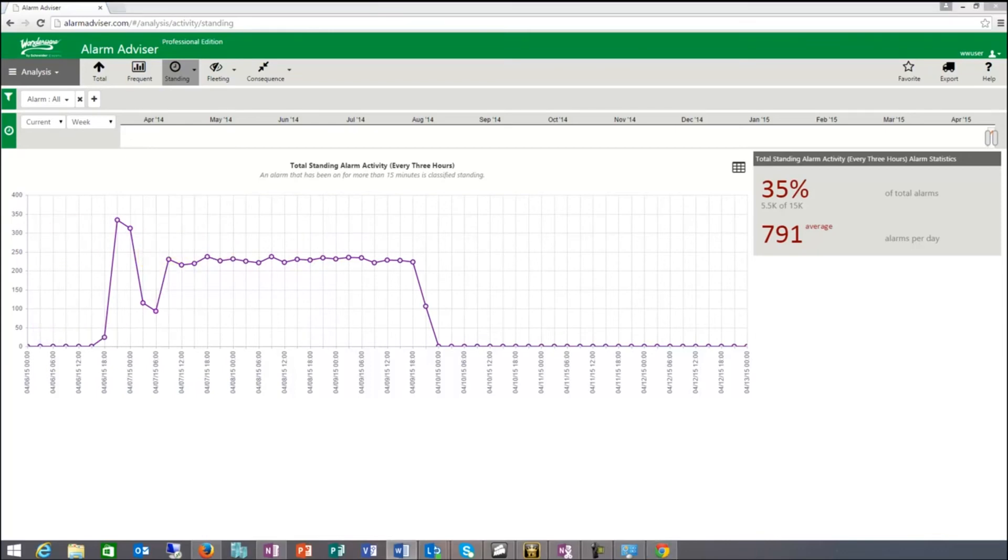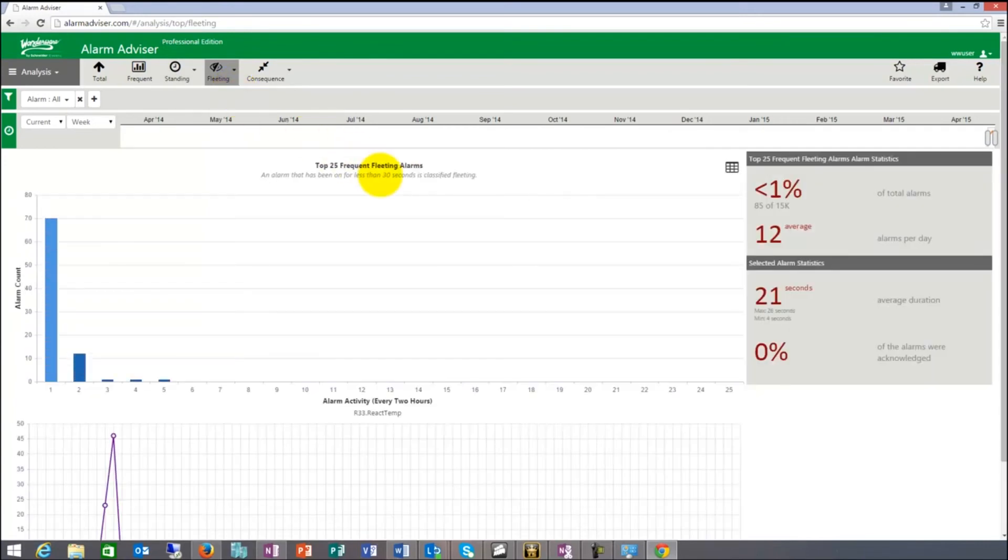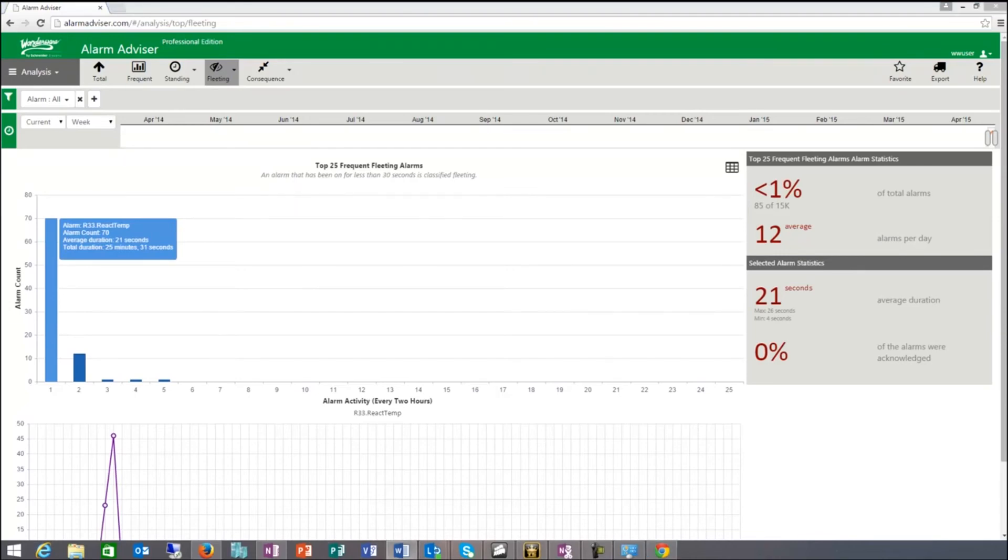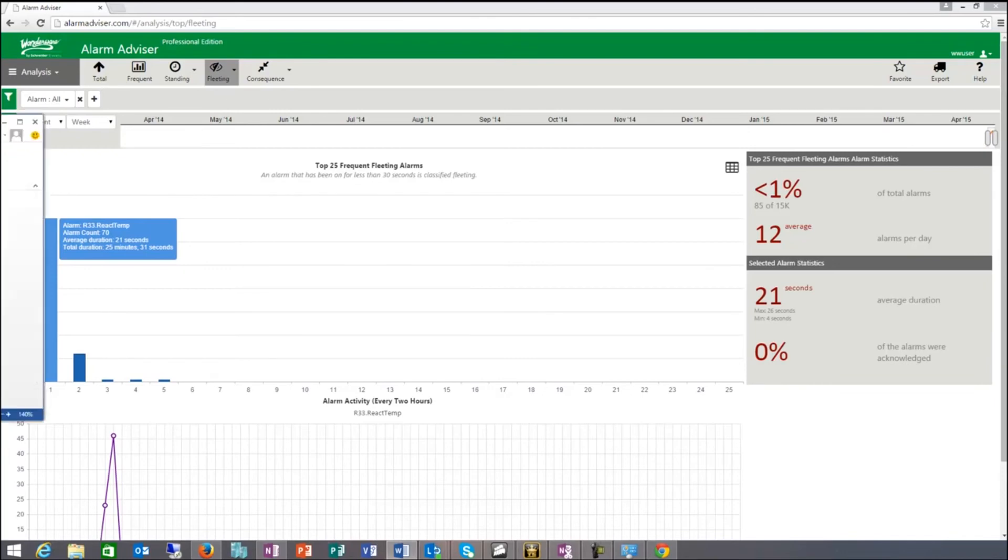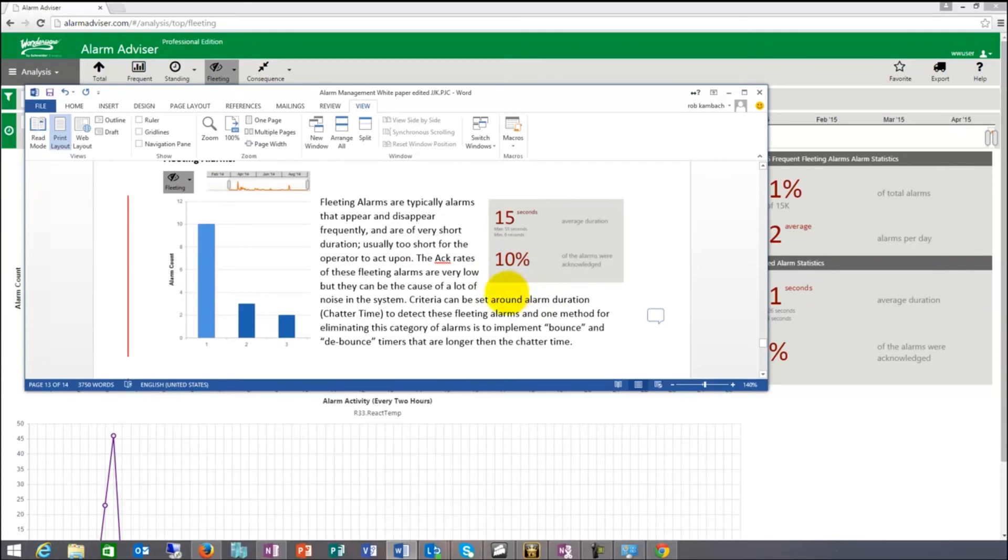The next one is fleeting. Fleeting is a definition, basically a system setting that you can do. And in this system, it's an alarm that has been on for less than 30 seconds. Let me take a quick look and show you fleeting in a document. Fleeting here is typical alarms that appear and disappear frequently and are very often short of duration. Too short for the operator to act upon. A lot of these alarms won't be acted. Typical ack rates, low in the low percentiles, are probably appropriate because the operator never had a chance to act them. They were gone before you could act them.